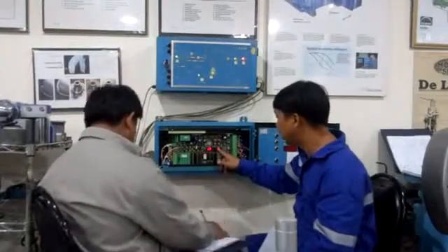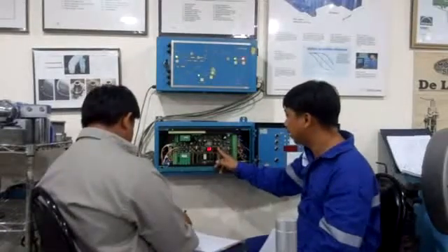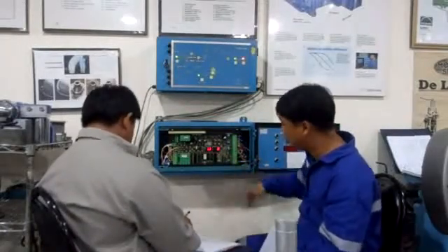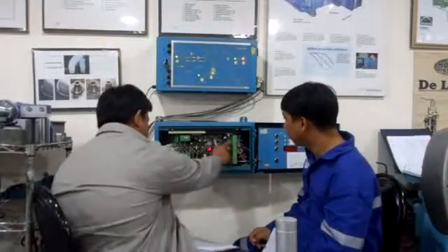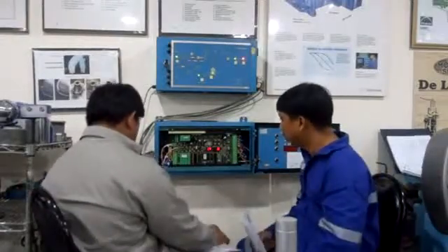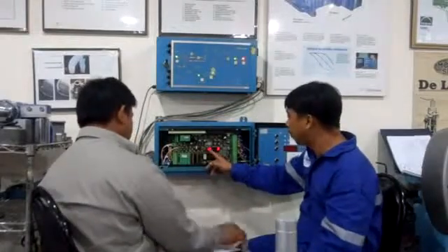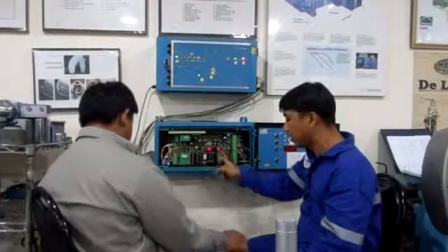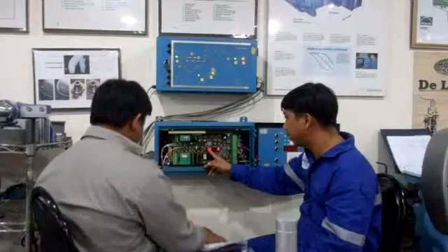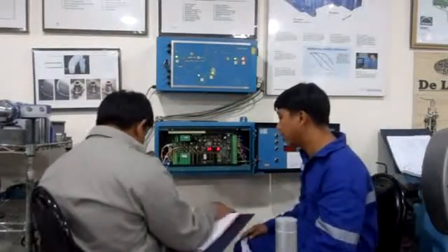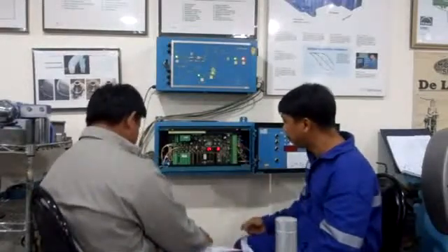At 1.3, we have the value, as indicated in our manual. When it is 0, what does it mean? Memory is correct. When it indicates E, the memory is faulty. We move again within each function by pushing push button 2. Now we have 1.4, and the value is 0. What is indicated in number 1 is about the memory. We are testing the memory of the EPC control unit.